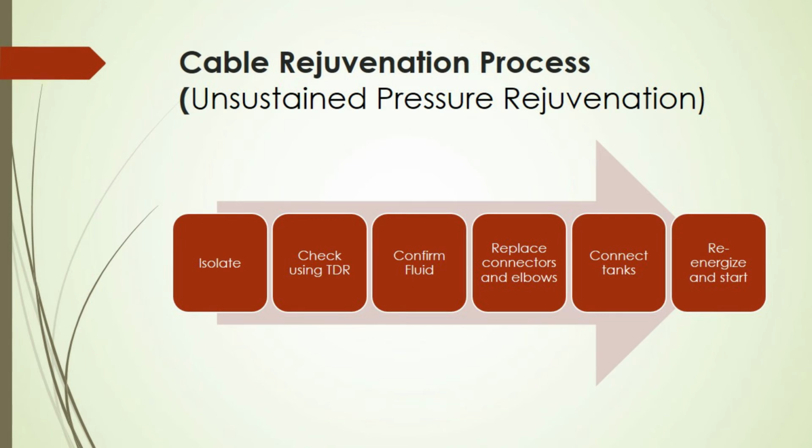Now, over the years, engineers have created a range of injection fluids and methodologies, allowing operators to deploy customized operations based on the cable type, occasion, or environment. The method may also be easily adapted to other cable arrangements, including splices and other connector types. In some circumstances, technicians would dig 6-foot square splice excavation trenches that are 4 feet deep in order to deal with those. And the impact of these pits on landscape is significantly less than that of trenching or digging, which is generally necessary for cable repair.